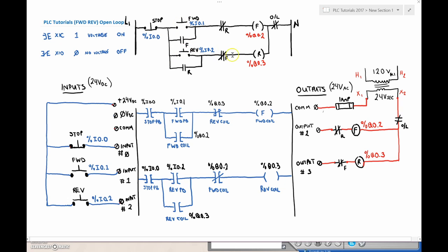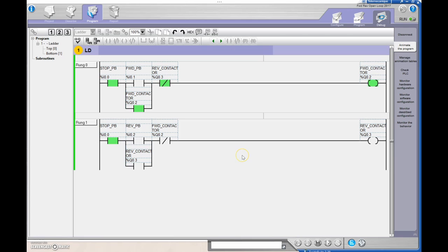The forward contactor is energized, so the XIO for forward is now open and I can't turn on the reverse contactor. Hitting the reverse does nothing — I have to hit the stop push button first. When I hit stop, it drops out the forward, the holding bit goes to zero, and the contactor turns off. Then hitting reverse turns on the opposing contactor.